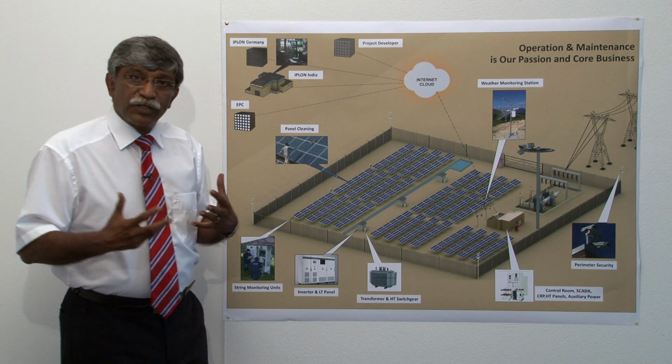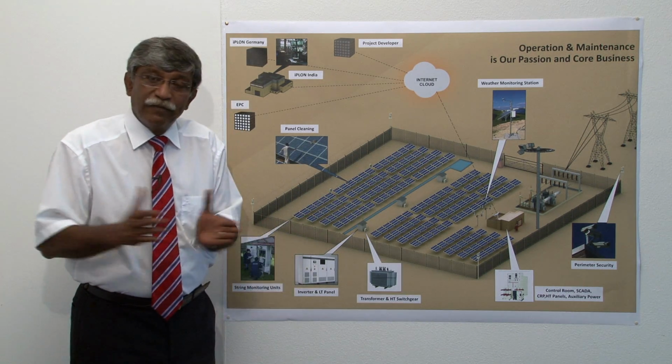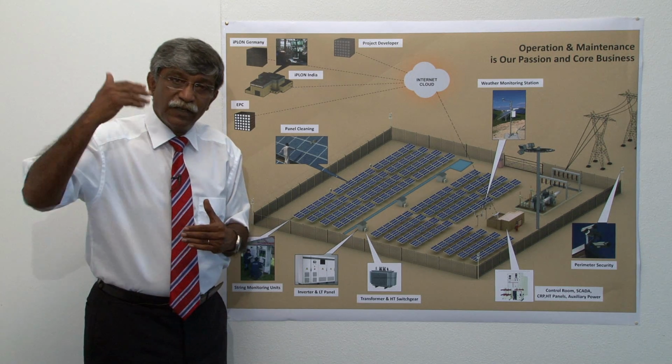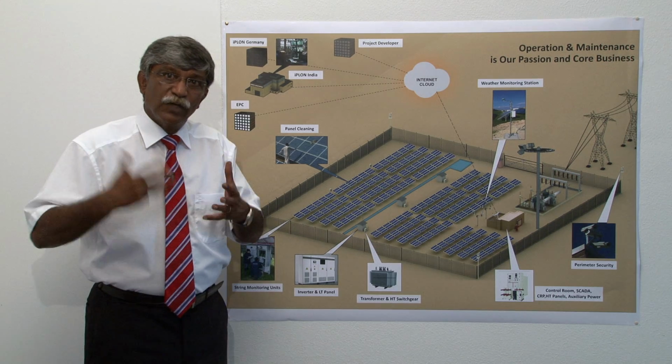Finally, I'd like to share with you our experience from the costs. Putting in a monitoring system with string monitoring, all these things can vary from 0.5 to about 2% of the total investment costs. It takes normally about 2 to 3 years for return of investment.